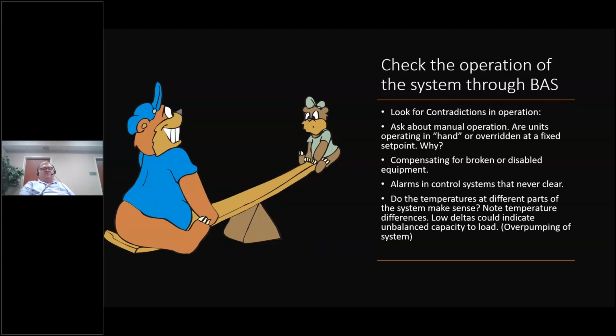Do the temperatures at different parts of the system make sense? Note the temperature differences. If you've got cold water coming out of the plant, going out to the building and coming back, you should have warmer water. But if you have, let's say, 45-degree water at the chiller and 42-degree water going out to the building, that doesn't make sense. Somewhere in between, it's pulled out 3 degrees of temperature.